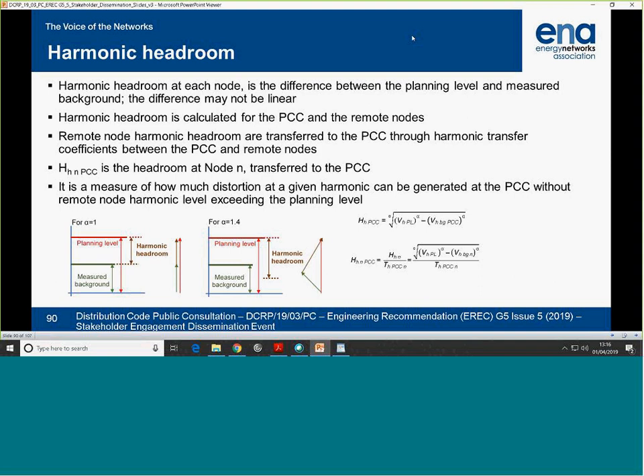We talked about the aggregation exponent this morning. For h up to 4th, we said alpha was unity, 1. If you do an arithmetic sum, that's what we get. So this is the background. The green line is the harmonic background, the existing harmonic level in the network before the new connection is made. The difference between planning and the background is the harmonic headroom, so you can use this to connect.